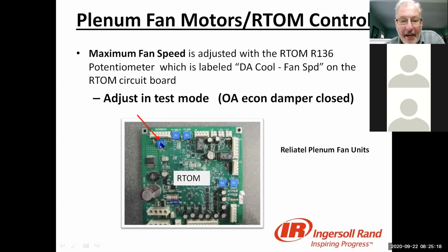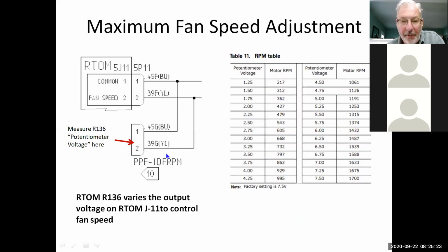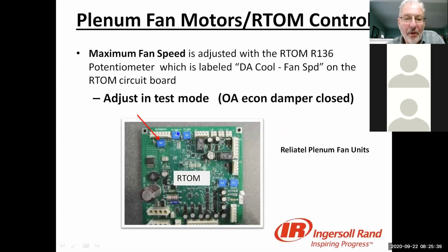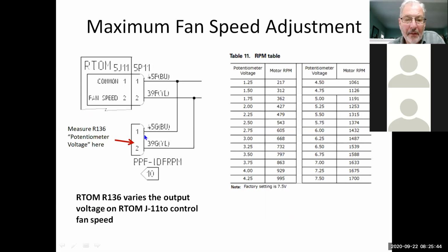If it's a Reliatel board, you want to adjust this potentiometer right here, and underneath the board, there's a yellow and a blue wire, 45G and 39G. What you do is you put your meter into this plug, this pigtail that's hanging down there, and adjust your motor to 6.5 volts. So go back to this potentiometer with your screwdriver and make an adjustment. When the meter reads 6.5 volts on these 2 pins, your blower's set. You should be all good to go, okay?